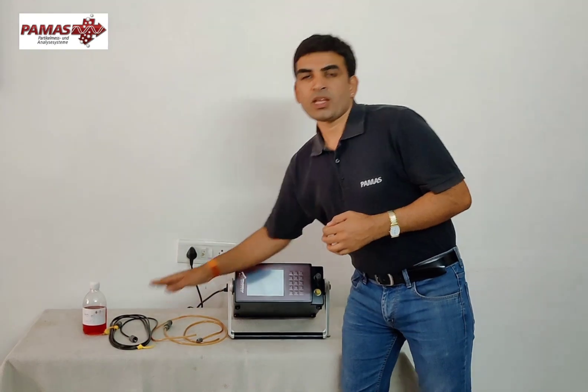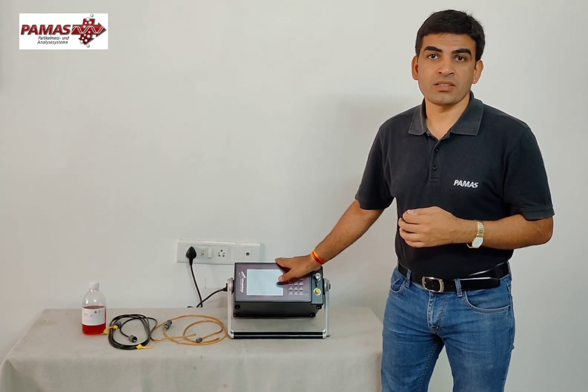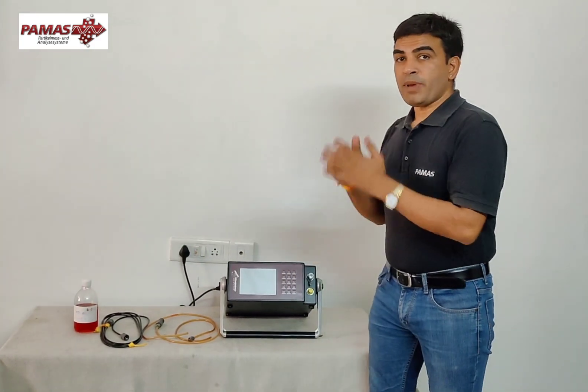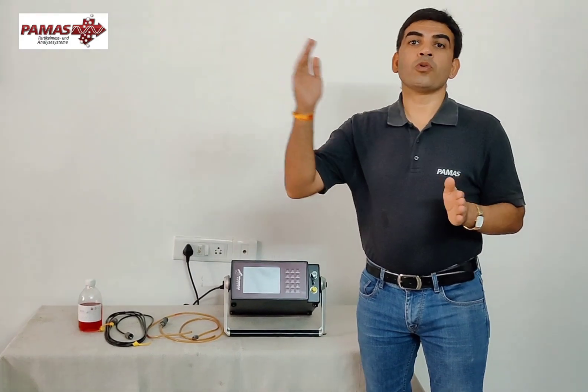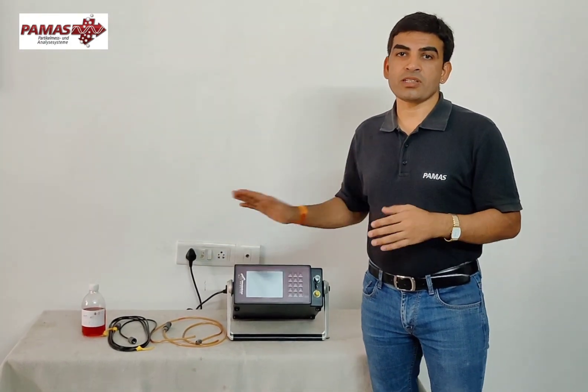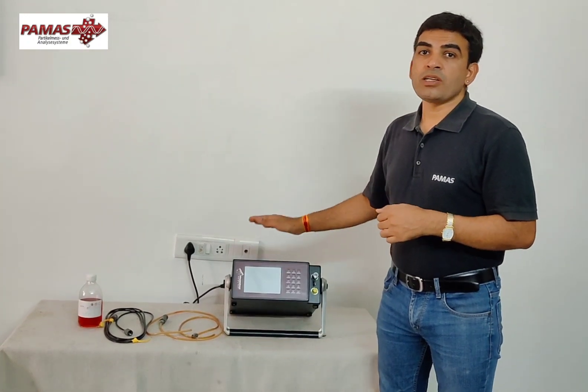With the Minimess coupling it will handle pressure up to 420 bar, meaning you can use this instrument from 0 to 420 bar — it can handle any pressure. Another feature is that it has internal memory.